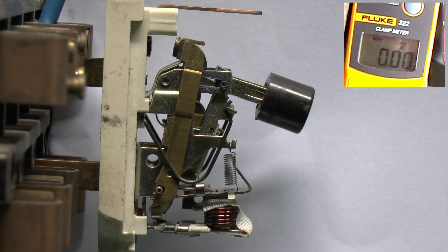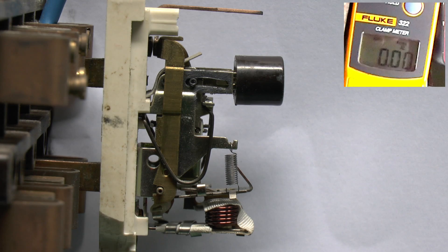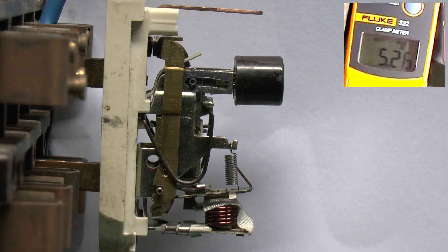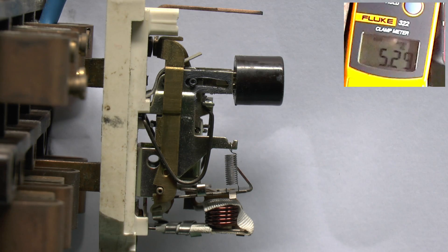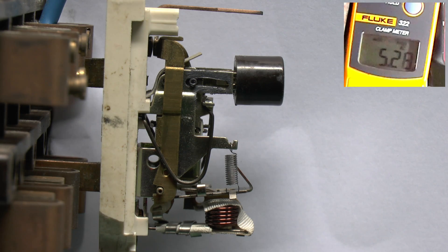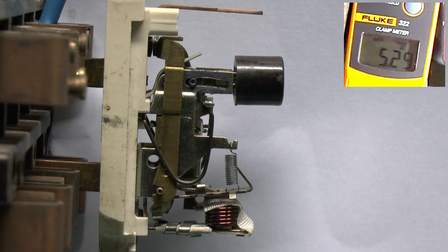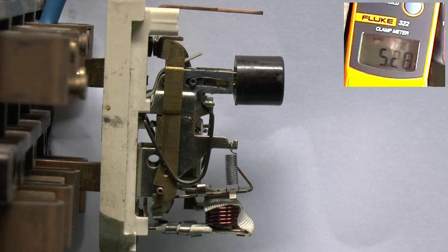I saw that tripped out there. And again it has obviously now disconnected the power, so that's now dropped back to zero. Now just reset there. And bearing in mind again it takes a few moments for this to cool, so we're waiting for that to cool back there. And again the breaker is now in the closed position. So just switch on the power again. Now just around the 5A mark there. And bearing in mind the breaker should be able to hold this indefinitely, bearing in mind it's a 5A breaker. And though we're slightly over 5 there so at 5.2 that shouldn't actually cause any problem. As these types of circuit breakers do not instantly trip once they get to the limit on the front of the device.